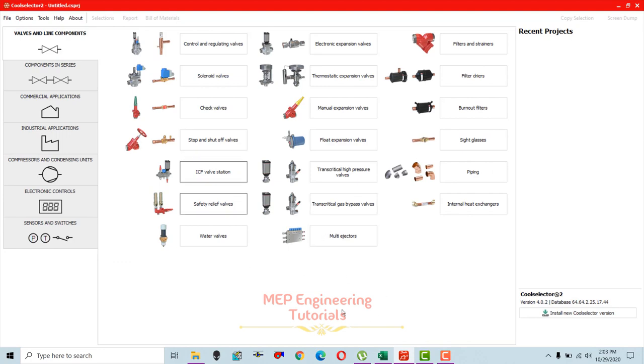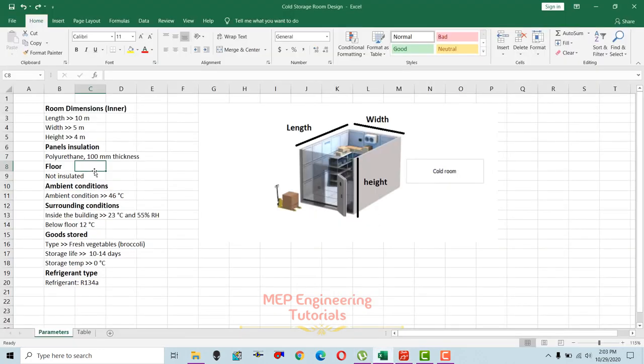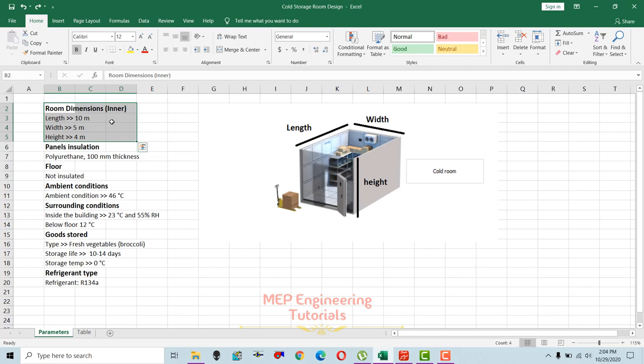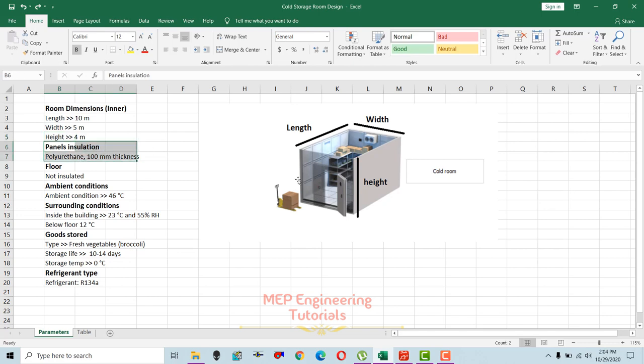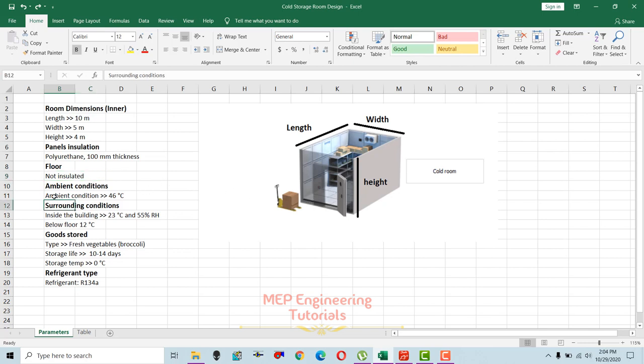First, let's move back to our Excel sheet. You can see this is our cold storage room which we are going to design. The room dimensions are given here — inner dimensions: length 10 meters, width 5 meters, height 4 meters. The panel insulation used is polyurethane, 100 mm thickness, and the floor is made of concrete with no insulation.